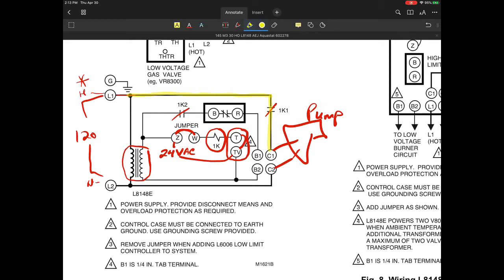And C2, of course, is your neutral. Now, what is different between the previous model and this one, in addition to this, is that B1 is now going to be your 24 volts. So this is now going to be powering 24 volts on the B1, and that's most likely going to be either 24 volts hot or the common, depending on which one you are using, and a lot of these aren't really grounded.